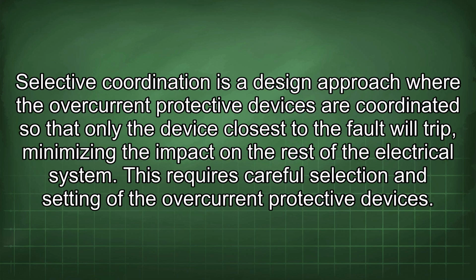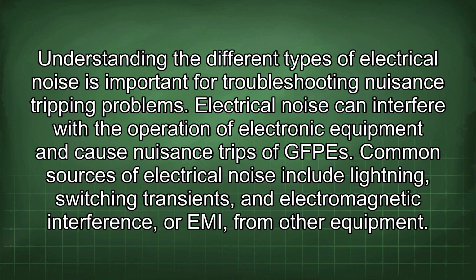Selective coordination is a design approach where the overcurrent protective devices are coordinated so that only the device closest to the fault will trip, minimizing the impact on the rest of the electrical system. This requires careful selection and setting of the overcurrent protective devices. Understanding the different types of electrical noise is important for troubleshooting nuisance tripping problems.